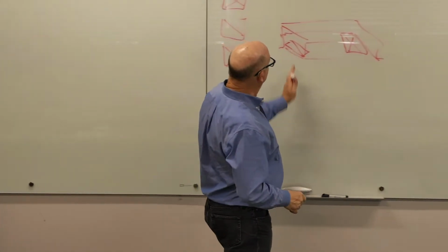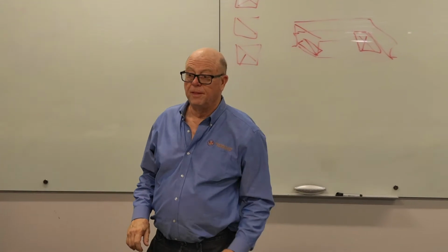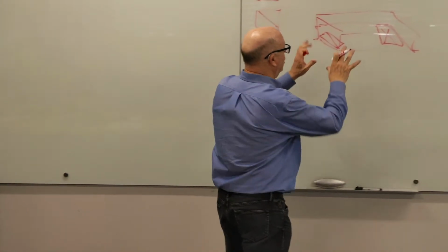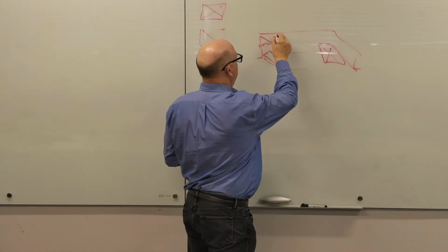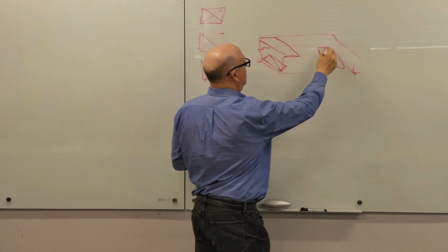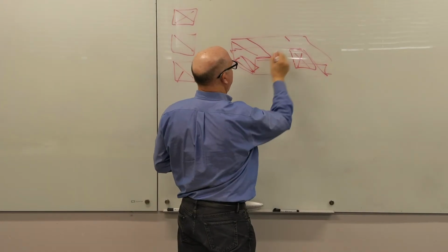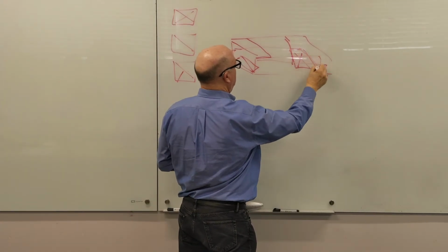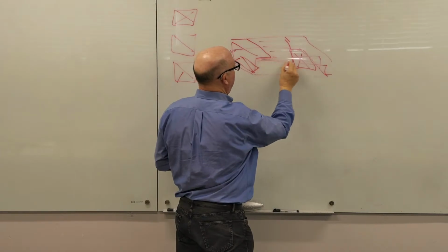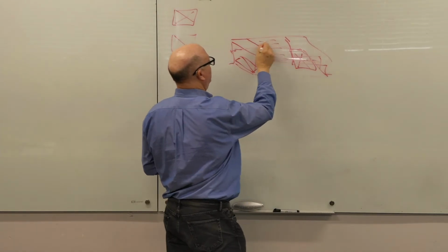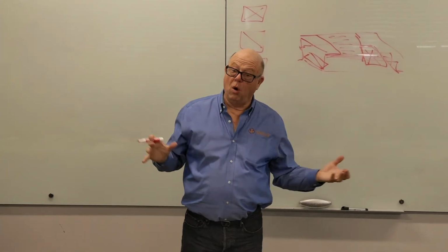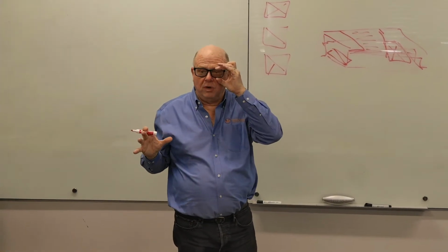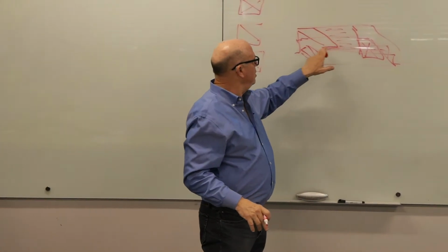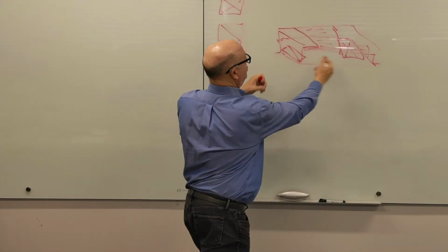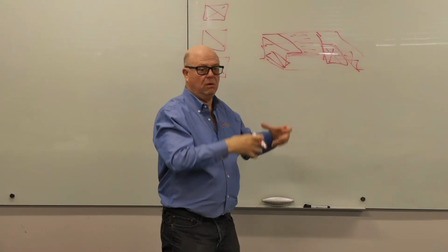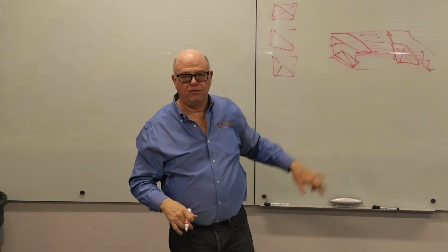So, we've got a return and a supply to our rooftop unit. And this curb is made to have an opening here and going across to the top of the curb and opening here. And then there might be a complete cover here if you're worried about weather covers, and just an opening there. Or they might rely on the rooftop unit itself to make a seal, in which case there'd be nothing there and you just have this and that, up to the top level of the rooftop unit.